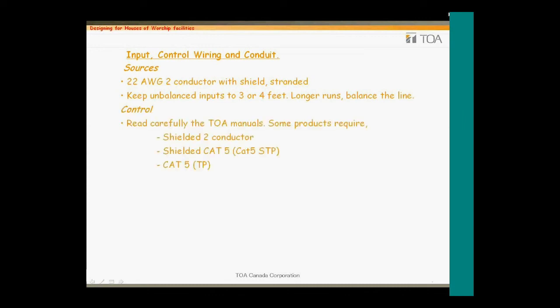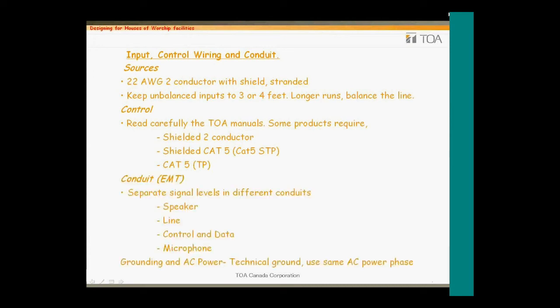Control wiring: check the documentation that comes with the TOA products, as not all wiring required for control is the same. Especially watch out for CAT5 requirements that are shielded — this is not a common type of wiring and may require a special order. When specifying conduit, keep in mind the different signal levels that require separate conduit systems. Do not mix unlike signal levels, or you may be in for a big surprise. One last thing on wiring is grounding: on large systems, have the electrician provide an isolated single ground point for the equipment rack. All grounding in the rack should be referenced to this single ground point to help prevent ground loop problems. Also have the electrician supply all electrical feeds from the same phase of the AC feed. In summary: same ground, same phase.